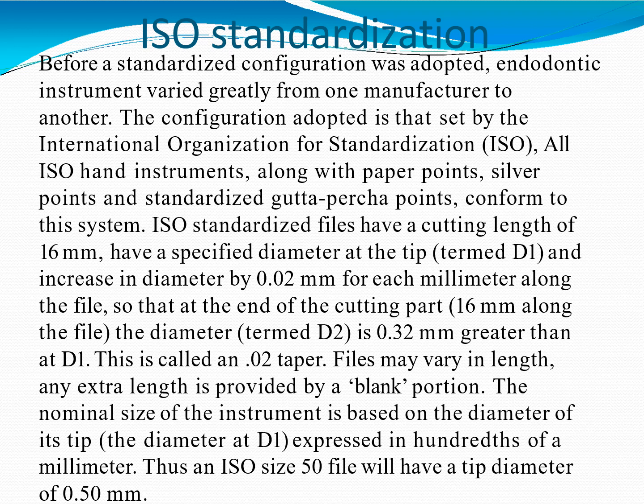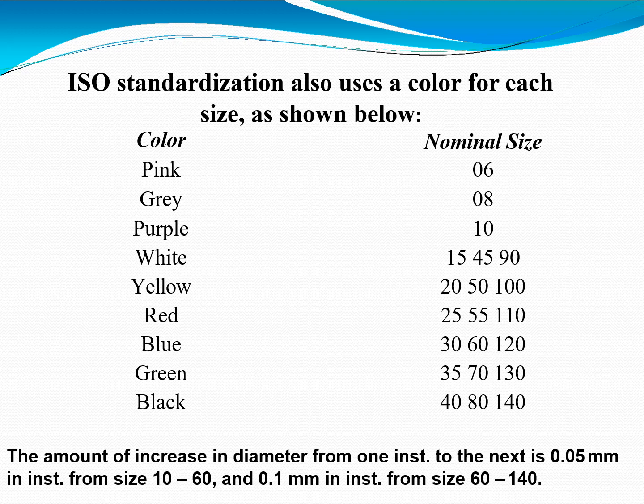ISO standardized files have a cutting length of 16 millimeters and a specified diameter at the tip, termed D1. There is an increase in diameter of 0.02 millimeters for each millimeter along the file, so that at the end of the cutting part — 16 millimeters along the file — the diameter, termed D2, is 0.32 millimeters greater than D1. This is called a 0.02 taper. Files may vary in length; any extra length is provided by a blank portion. The nominal size of the instrument is based on the diameter at D1, expressed in hundredths of a millimeter. Thus an ISO size 50 file will have a tip diameter of 0.50 mm.